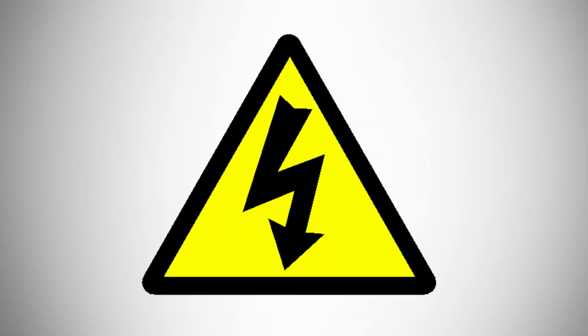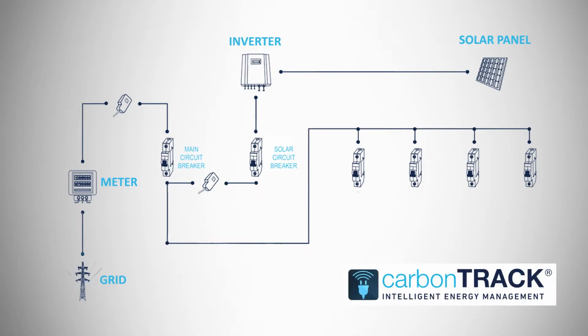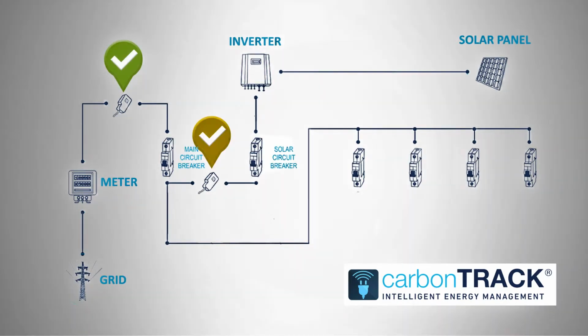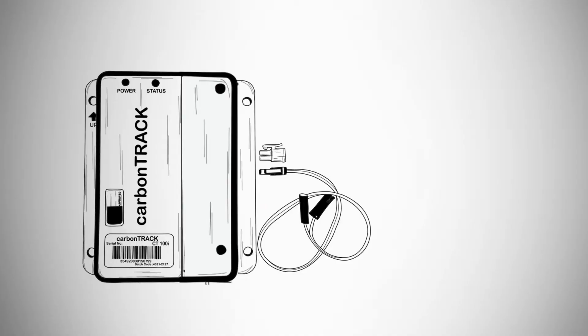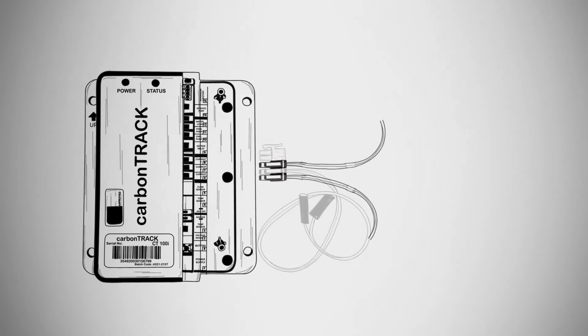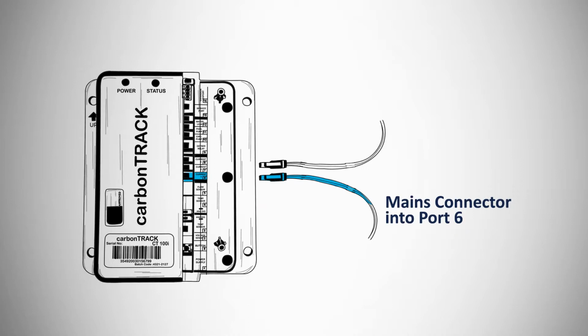At this point, please ensure that the power is turned off before you continue. Install 1 current clamp on the mains wire between the meter and the mains breaker. Install another CT on the live output wire of the inverter. Next, remove the CT100i service cover. Run both current clamp cables into the CT100i enclosure. Plug the mains clamp connector into port number 6 of the CT100i. Plug the solar clamp connector into port number 7.